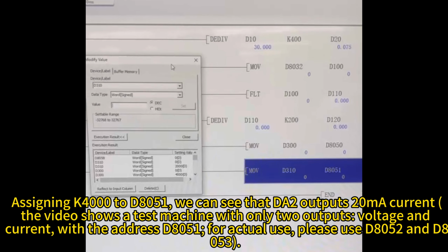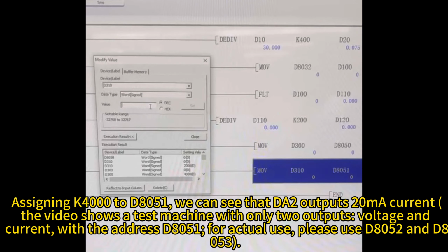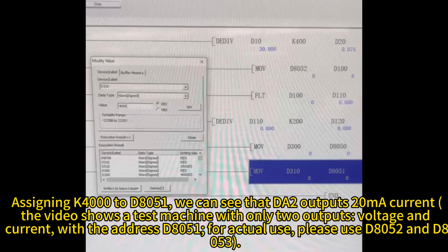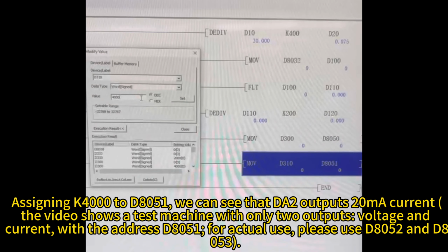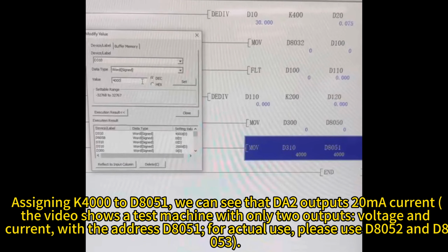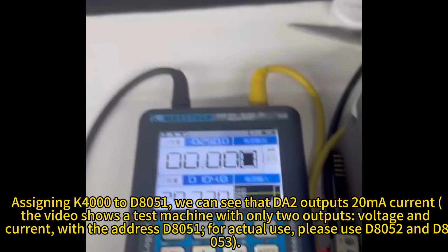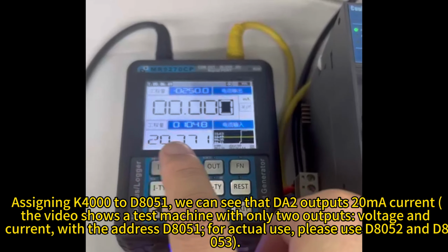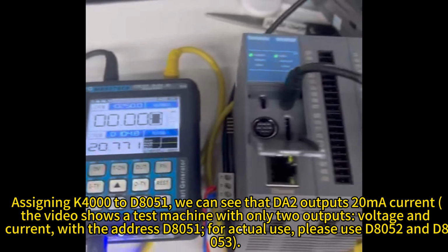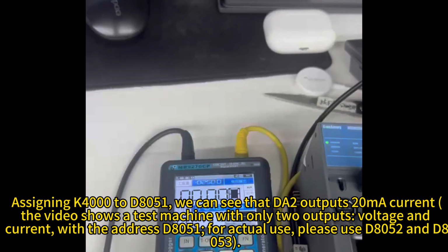Assigning K4000 to D8051, we can see that DA2 outputs 20 mA current. The video shows a test machine with only 2 outputs, voltage and current, with the address D8051. For actual use, please use D8052 and D8053.